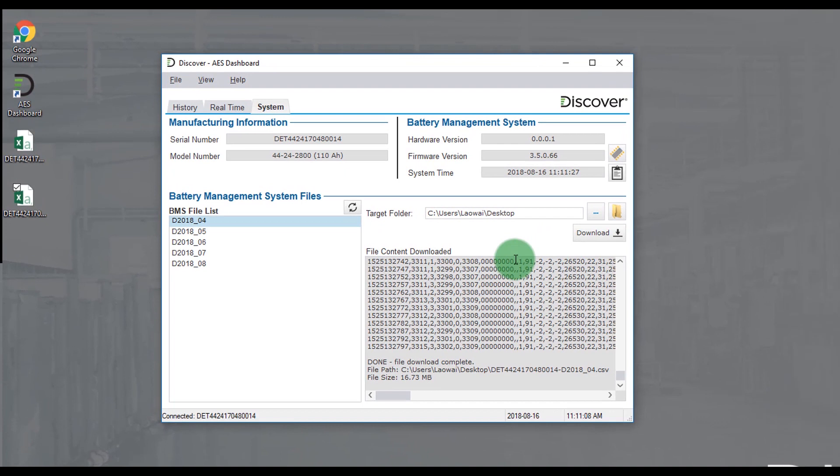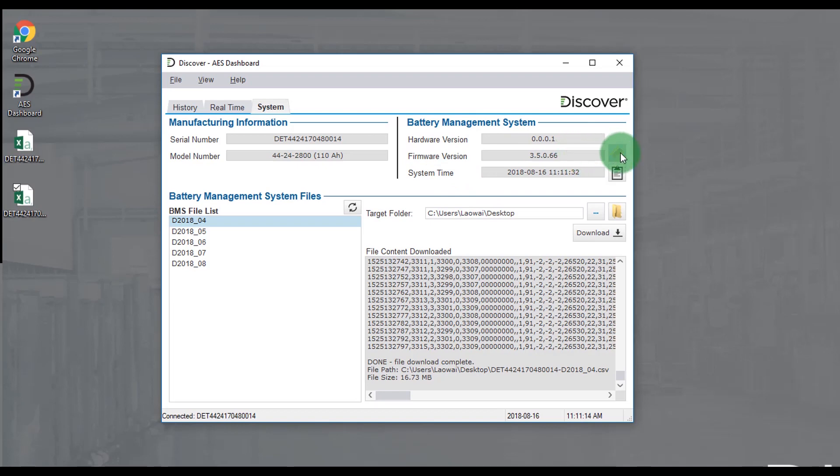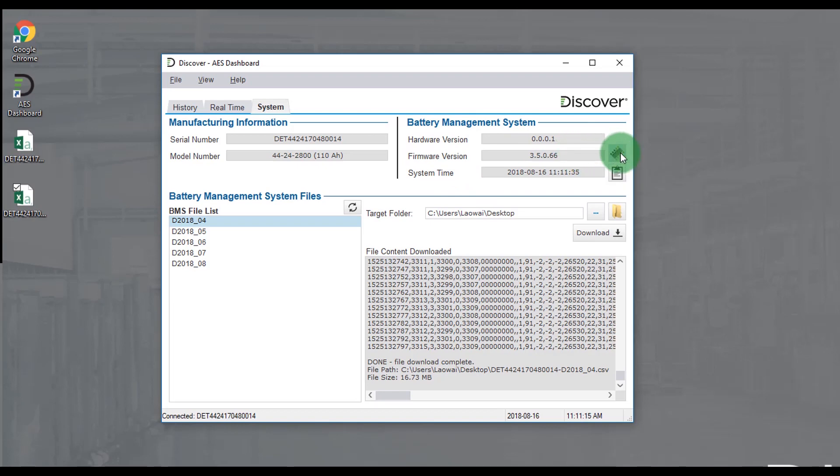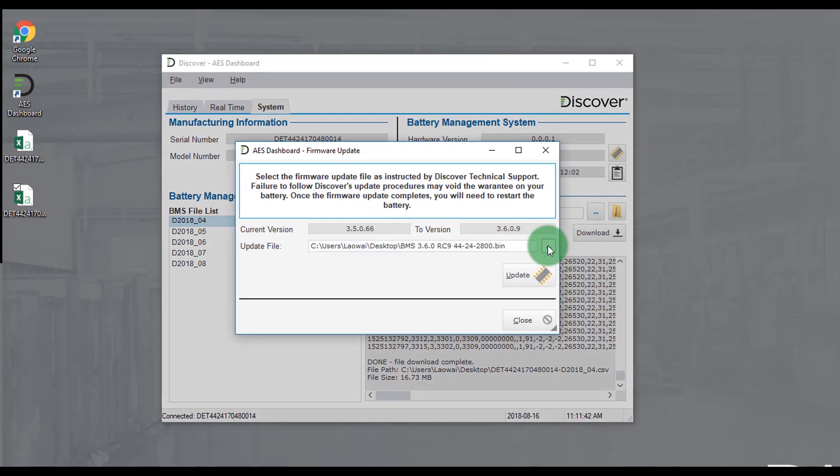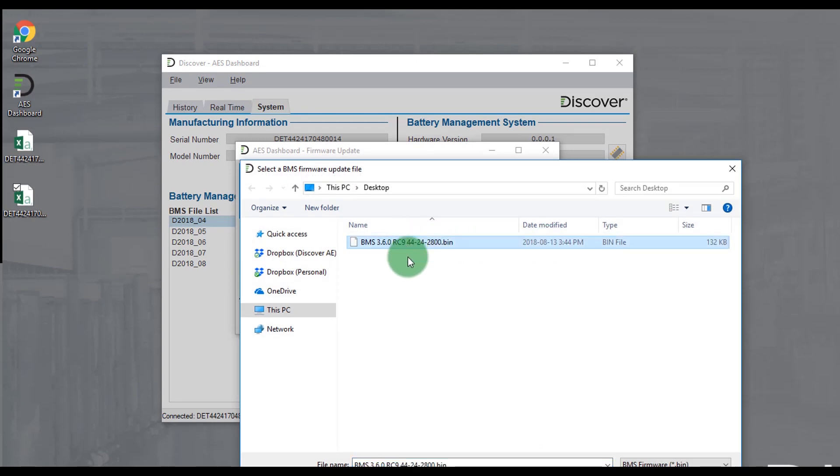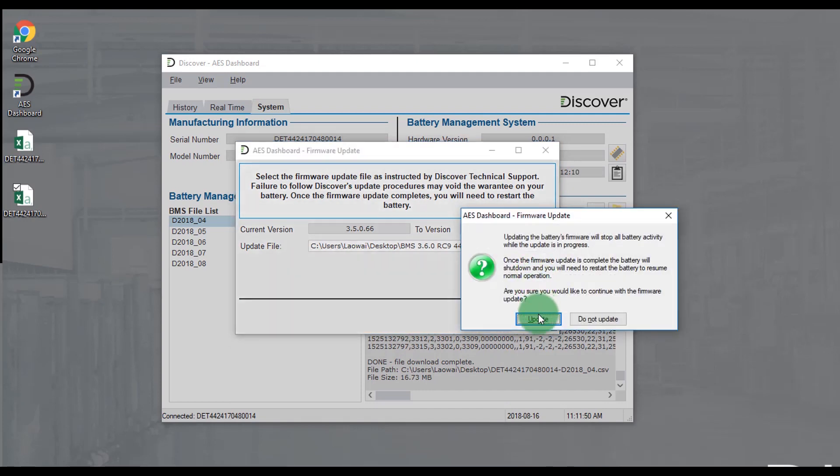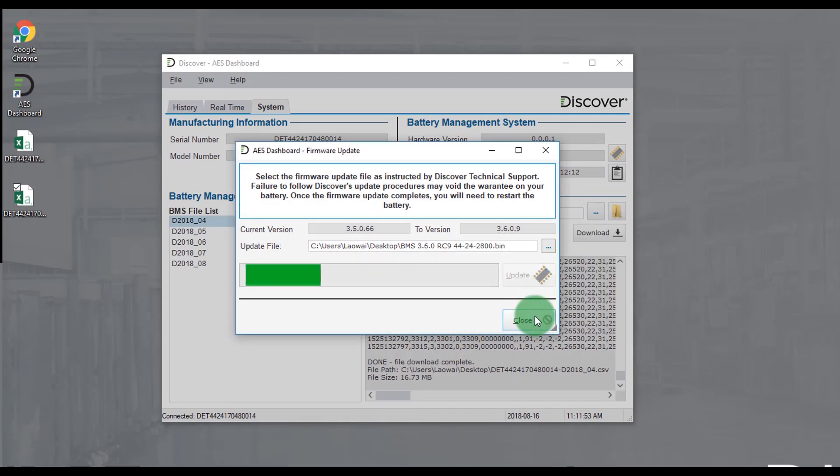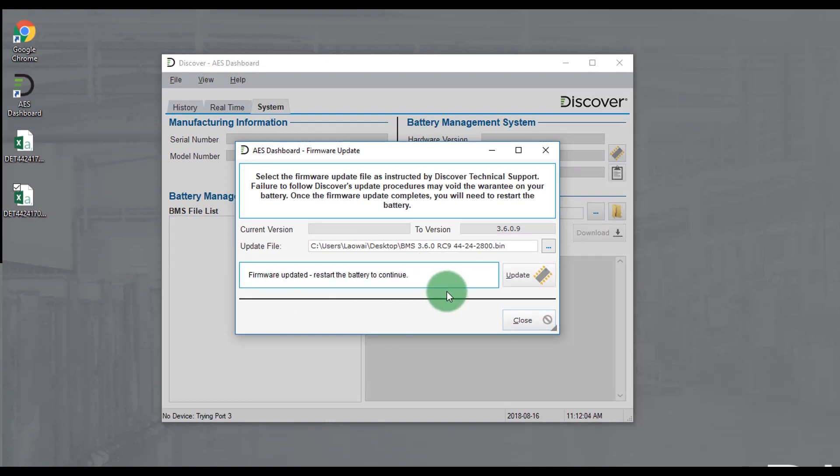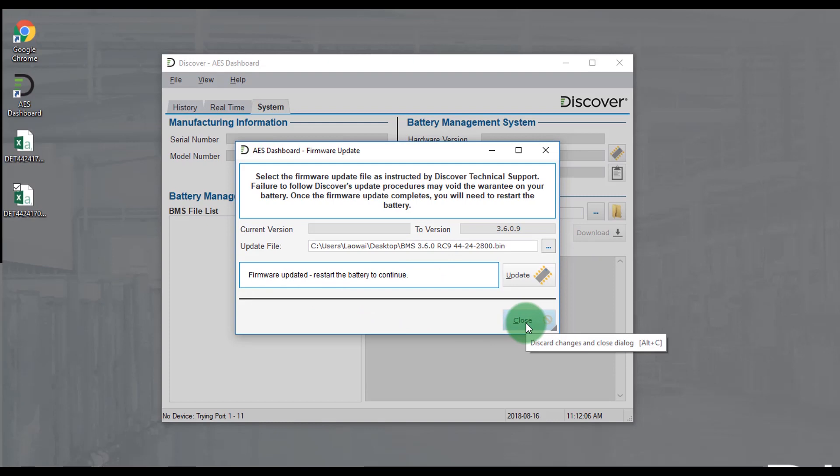The system tab is also where the battery firmware can be updated. Right next to the firmware version there's a little icon. This will take you to the firmware update interface. Ensure that you've got the latest binary downloaded from the website for your battery. Let the program know where this file is. Click update. When the updating is complete the battery will turn off and you'll notice that the program is no longer communicating with it. Just reach down and turn the battery back on and it should connect back up.